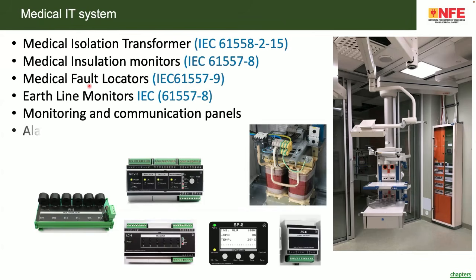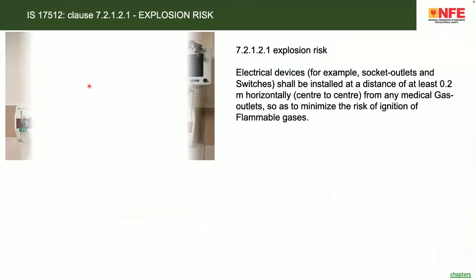Earth line monitors, a monitoring and communication panel, and an alarm transfer unit, all these things together form a separate panel, and the power supply to some of the plug sockets in the operation theater and the ICUs is to be used through this specific panel. The maximum capacity of the panel is 10 kVA. Higher capacity equipment is not supposed to be connected to this particular panel. The panel has to be within 25 meters of its usage, meaning you have to keep it closer to the location where you are going to use electricity. The leakage current has to be kept minimum. So many additional safety measures are included in the medical IT system. So the medical IT system is a mandatory requirement.